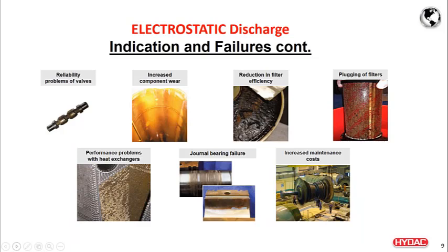Now, there is a fine line between the varnish generation due to the electrostatic discharges or the temperature, having constant higher temperature. The constant higher temperature could be cooling related issues, but the electrostatic discharge and the varnish are also related to each other. And when you have electrostatic discharge, the temperature is anywhere between 2,000 to 3,000 Kelvin. That localized temperature is going to burn the fluid and increase your TAN number, as well as generate the varnish.